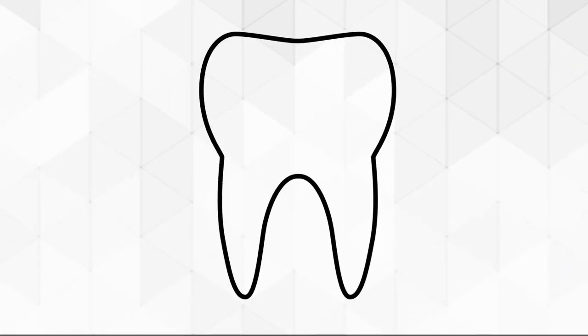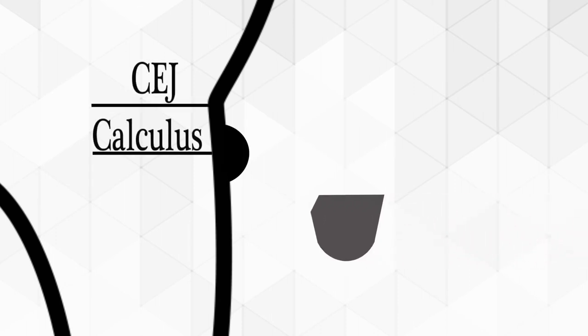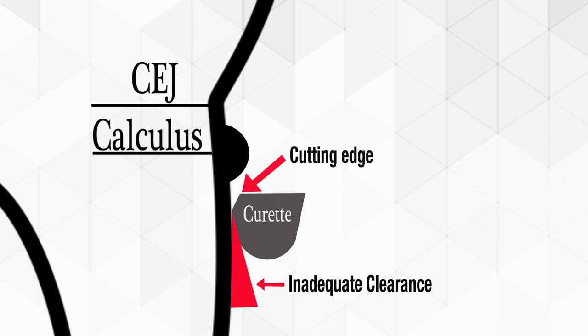If the cutting edge still does not bite into the acrylic test stick or cannot be used at the proper angle of activation during the clinical use of the instrument, then the problem is now one of a significant degree of inadequate clearance on the lateral side of the cutting blade below the cutting edge, as shown. Clearance is the space developed between the tooth and the side of the blade immediately behind the cutting edge when it is in function. The two surfaces involved form an angle measured in degrees known as the clearance angle.